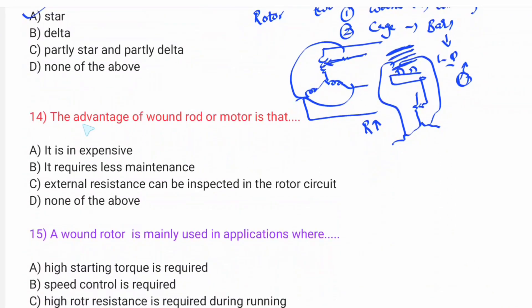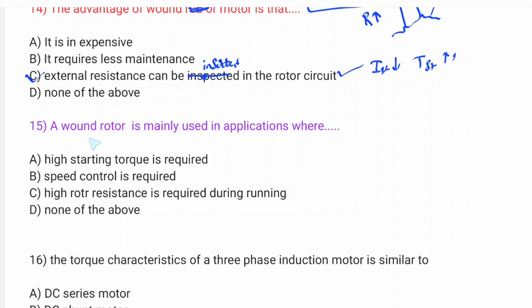The advantage of a wound rotor motor is that external resistance can be inserted in the rotor circuit. This external resistance changes the rotor circuit resistance, which increases the starting torque. The wound rotor motor is normally used in applications where high starting torque is required.